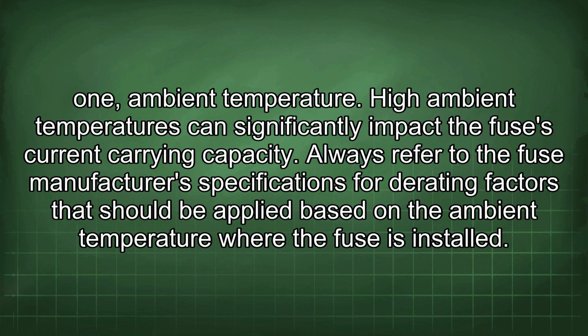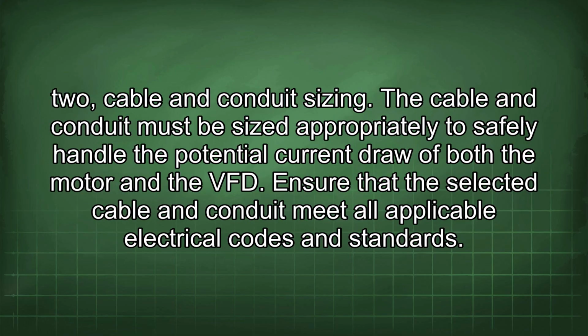1. Ambient temperature. High ambient temperatures can significantly impact the fuse's current carrying capacity. Always refer to the fuse manufacturer's specifications for derating factors that should be applied based on the ambient temperature where the fuse is installed. 2. Cable and conduit sizing. The cable and conduit must be sized appropriately to safely handle the potential current draw of both the motor and the VFD. Ensure that the selected cable and conduit meet all applicable electrical codes and standards.